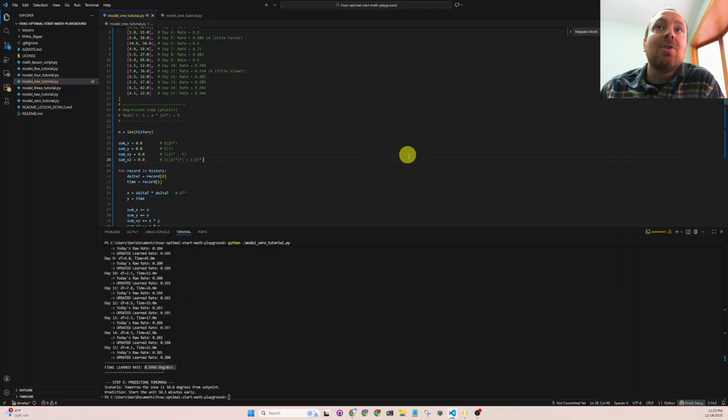So when the building's colder or warmer, and that delta temperature between the zone temp and the occupied heat or occupied cool set point is bigger, the rate that it takes to warm up that zone isn't a perfectly linear curve like our previous model, which just assumes a flat line. We actually need a curved line, which would be this quadratic model that stems from this squared delta temperature.